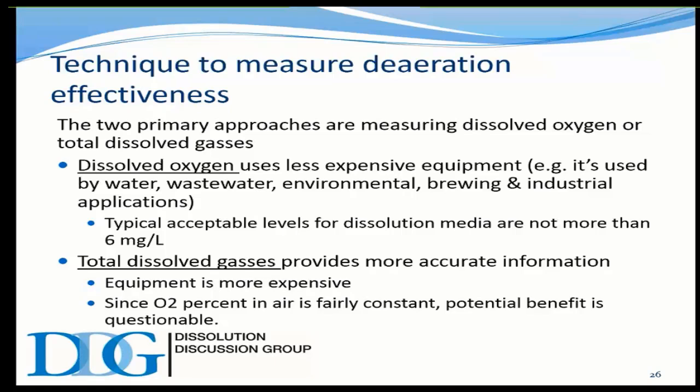Well, what you'll see here is that we're going to talk about some measurement techniques. Some people have relied on the PVT itself because it is so sensitive to dissolved gases to let them know if their level of deaeration is effective. I'm a little bit cautious about that, mainly because it may be confused with something else interfering with the dissolution apparatus, like something vibrating on the bench, which also elevates test results.